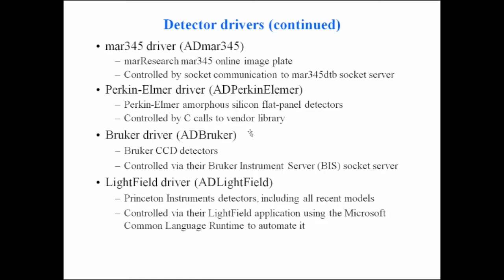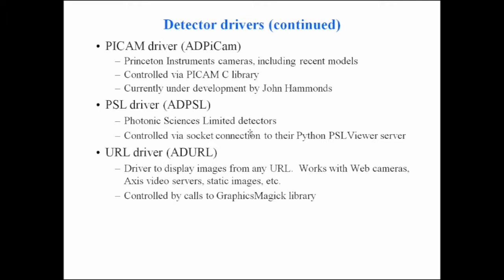The Lightfield application is written and automated using C# objects controlled from C++, so we can run it from EPICS. We're using this on our beamline. There's also a new driver John Hammons is working on for PI Cam — the replacement for PVCam, for Princeton Instruments cameras only — providing a way to talk to new Princeton cameras without Lightfield, directly through a library. The disadvantage of Lightfield is it costs around $4,000 just to buy the software.